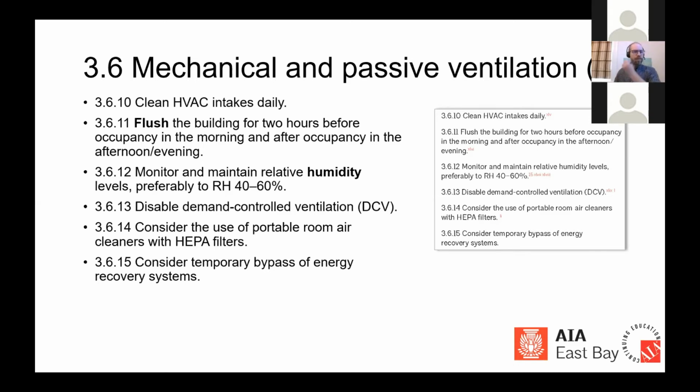Now, the next one is about the relative humidity levels. This is following ASHRAE, preferably within a relative humidity of 40 to 60%. In the document itself, I don't know if you can see this as well as I can on my screen, but you'll see in red these footnotes. With these footnotes, you can always look up the source of information from which many of these were derived.